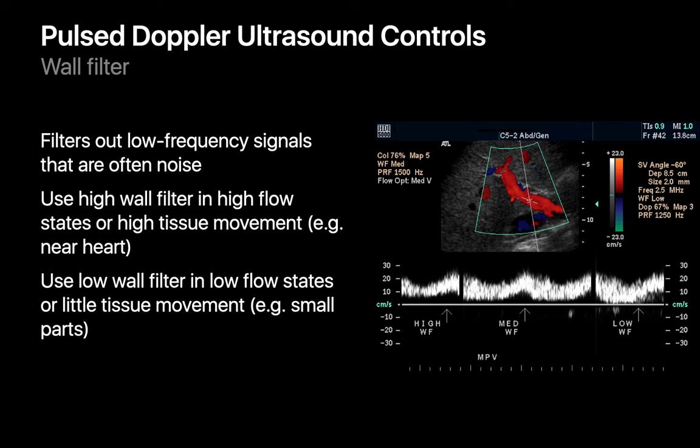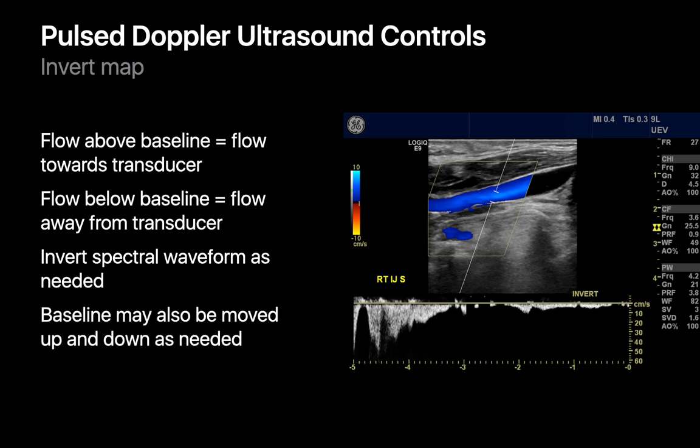The wall filter helps reduce noise in your spectral Doppler waveform caused by extraneous nearby sources of motion, such as a moving heart nearby. This noise can be reduced by filtering out high or low frequency motion corresponding to how rapidly the extraneous motion is occurring, as long as that velocity range doesn't overlap with the flow velocity you're studying. Finally, map invert assigns whether flow towards your transducer will be drawn above or below the horizontal baseline, and also permits you to move the baseline away from 0 cm/s if desired.